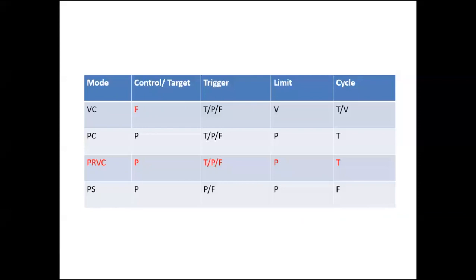Flow. What is the trigger? Either time or flow. It can be time, pressure, or flow. In any mode, you can have all these three: time, pressure, flow.